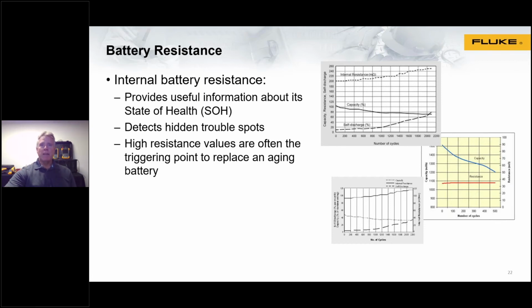There's two ways of making the measurements, which we'll come to in a little bit, but essentially what's very useful here and what's key is to trend the measurements. Because if the trend suddenly takes a sharp change in slope, that can signal that end of life of a battery draws near, and you can take proactive action versus an out-and-out failure. The internal resistance of batteries will increase. So the trend that we're looking at is an increase in internal resistance.